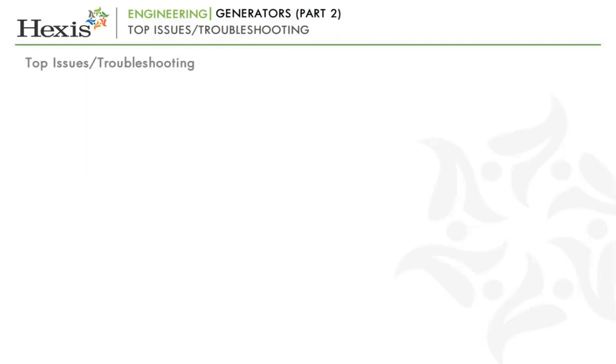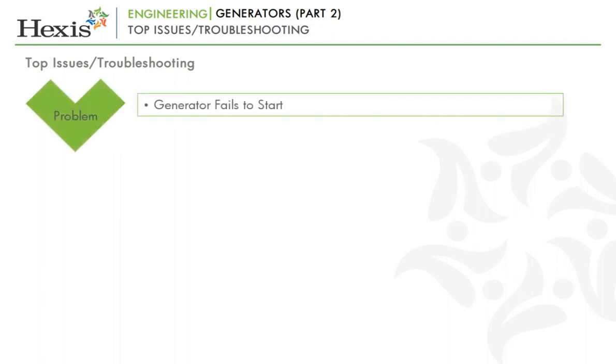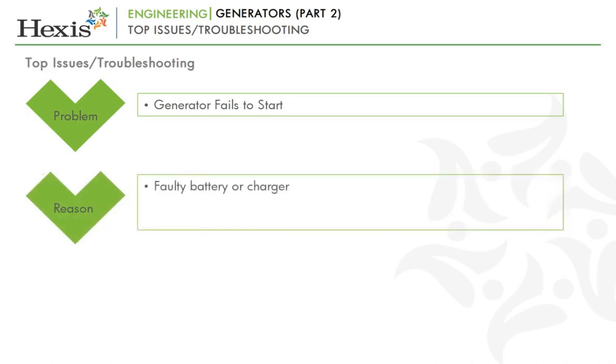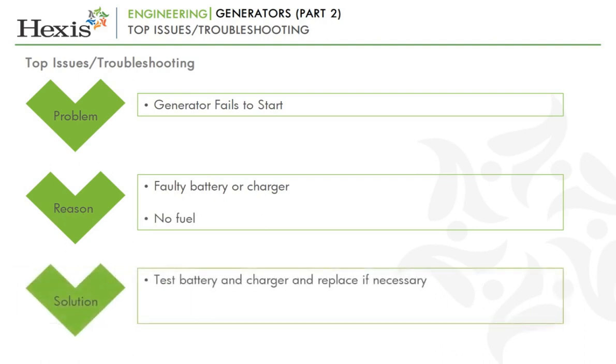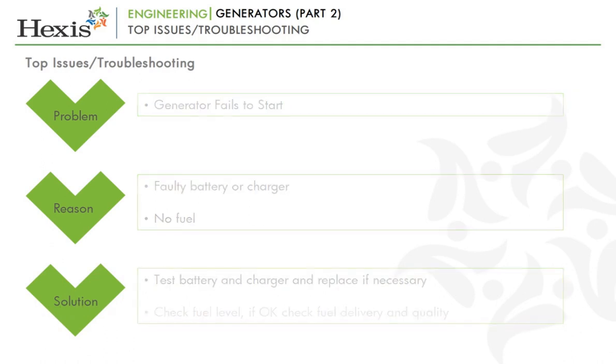Let's now look at the top issues caused to the diesel generators and the ways to troubleshoot these issues. Problem: generator fails to start. Reason: the reason could be due to faulty battery or charger, or there is no fuel. Solution: test battery and charger and replace if necessary. Check fuel level. If okay, check fuel delivery and quality.